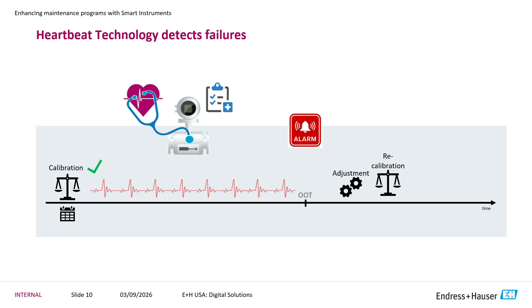But what we really want to get into is being able to have that diagnostics and utilize all that data to actually start doing predictive—prescriptive—work. We can tell when the sensor is going to need to be calibrated, and we know when it's likely to fail. This is all within the data collection of that heartbeat technology. There's lots of diagnostics and data coming out that would need to be analyzed, but this is the direction we really want to move toward, so we're optimizing the calibration cycles.